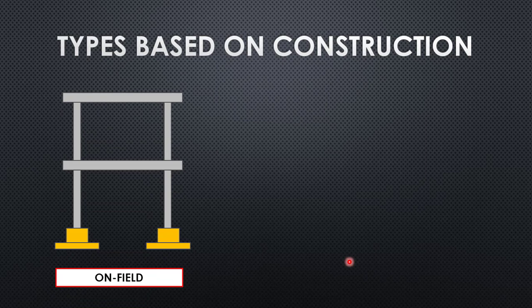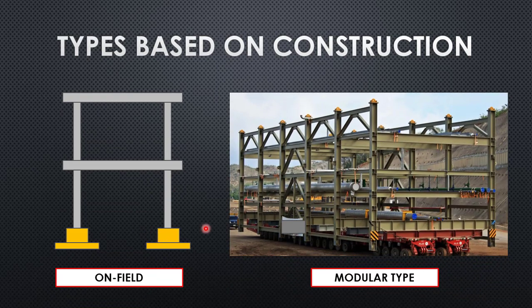Now we'll see the types of pipe rack based on construction. We have two types: the on-field pipe rack and the modular pipe rack. On-field pipe rack is constructed from scratch in the field — from zero to completion. Modular pipe rack is different: only the civil foundations are constructed in the field, while the entire pipe rack structure comes from outside. A vendor manufactures the entire pipe rack elsewhere and ships it to you, so you just receive and install it. This saves construction time in your project.